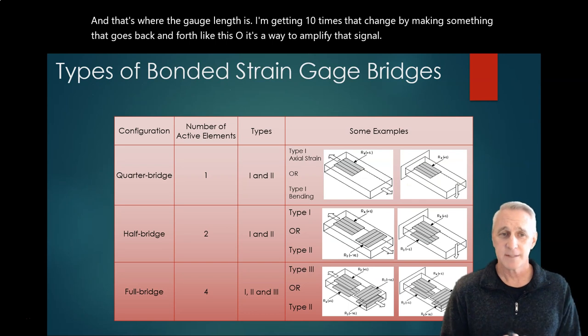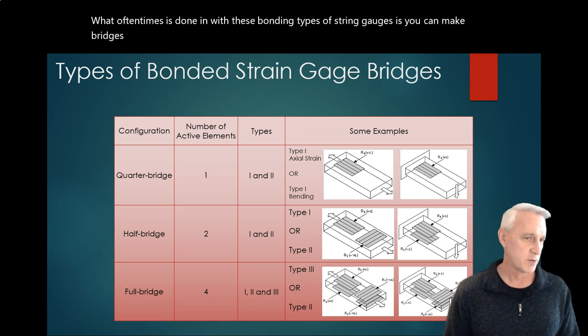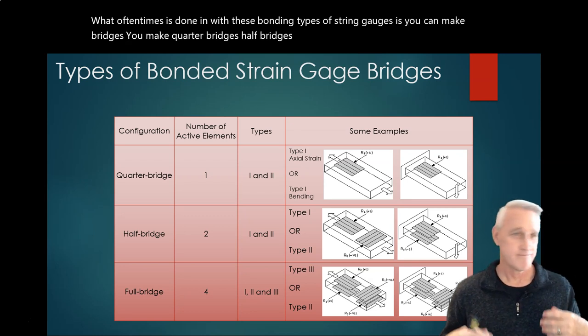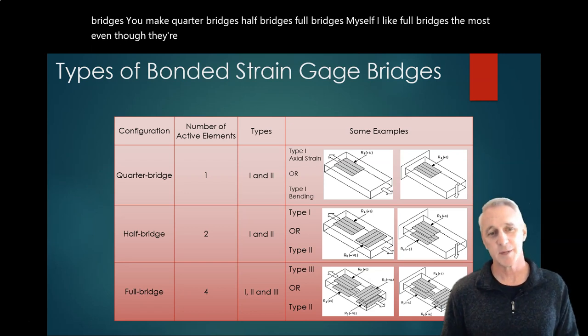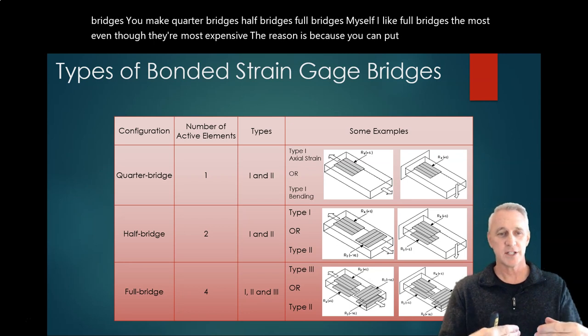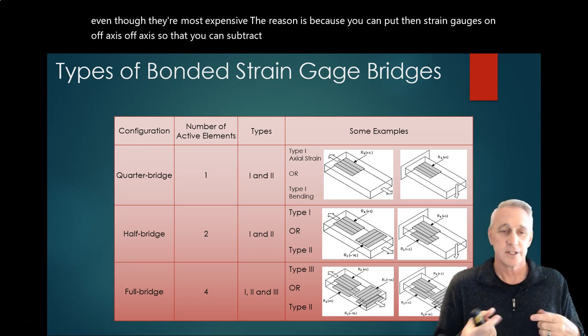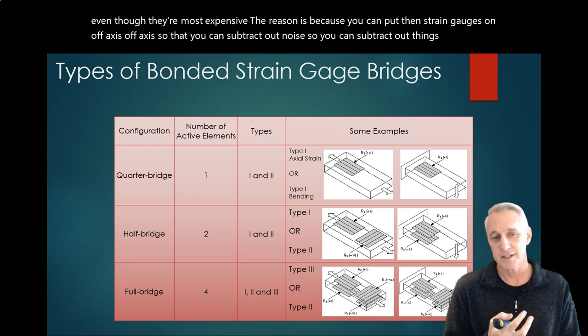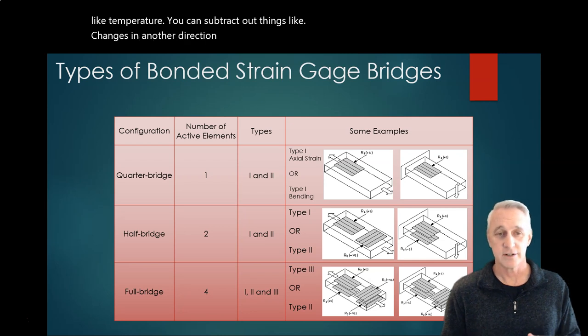Now, what oftentimes is done with these bonding types of strain gauges is you can make bridges. You can make quarter bridges, half bridges, full bridges. Myself, I like full bridges the most, even though they're most expensive. The reason is because you can put strain gauges on off axes so that you can subtract out noise. So you can subtract out things like temperature. You can subtract out things like changes in another direction that's not on the axis that you're interested in.